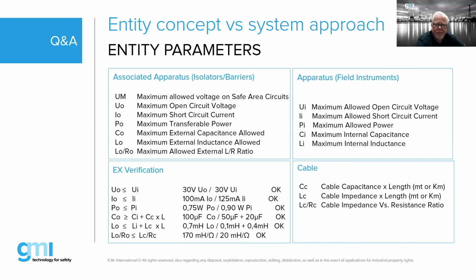And so you have to take. We had a question about cabling. Cabling also needs to be taken into account, right, Bob? That's correct. We need to understand the resistance and the capacitance, the energy stored within the cable. So we take into account the stored energy in a non-simple device, right? But we also have stored energy within the cable, so we have to take that into consideration. And again, that's one of the big issues that people forget: we don't take that into account. So we need to make sure that we understand that.